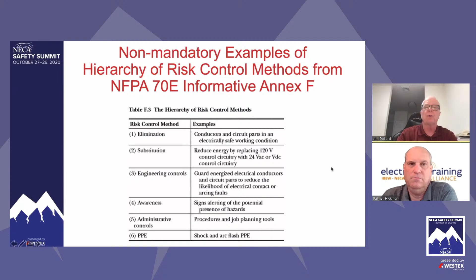After an incident, any contractor that looks at those kits to get that done, and there's plenty of them out there, to remotely open and then remotely rack and remotely close, they would wish that they invested in one of those kits to get it done. So the first method is elimination. It's the most effective, and it is in line with NECA's safety policy. NECA tells us it is the best practice and that we must eliminate whenever achievable, which means getting that owner and convincing that owner, actually training that owner. And when we train that owner, when we explain to them that they could lose their equipment, there could be injury, there could be lawsuits, then they begin to understand that we truly are the best value.